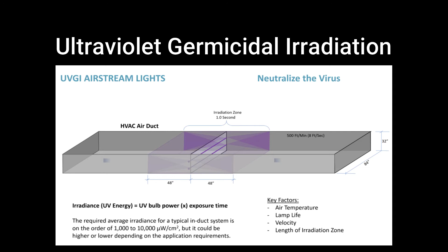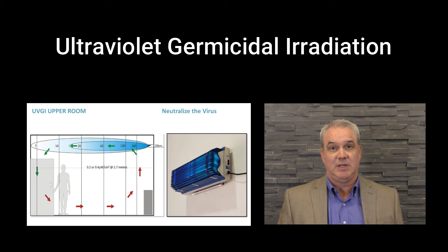Another means of utilizing UVC is by using light fixtures that target the upper part of a room. This solution is referred to as upper air or upper room UVC systems. These systems are designed to focus the UVC light in the upper part of the room, inactivating airborne infectious agents that reach the lighted zone. The lower part of the room is kept relatively UVC free, minimizing exposure to persons below. Upper air UVC is predominantly used in healthcare settings.